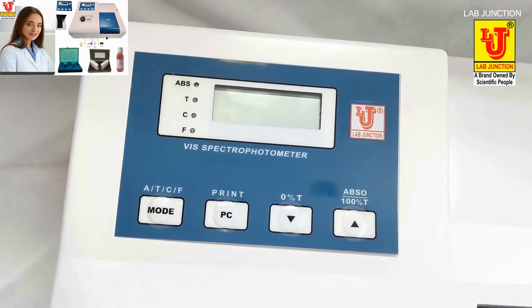A spectrophotometer is an instrument that measures the amount of light absorbed by a sample. Spectrophotometer techniques are mostly used to measure the concentration of solutes in solution by measuring the amount of light absorbed by the solution in a cuvette placed in the spectrophotometer. The technique measures light intensity as a function of wavelength. It does this by diffracting the light beam into a spectrum of wavelengths, detecting the intensities with a charge-coupled device, and displaying the result as a graph on the display device.